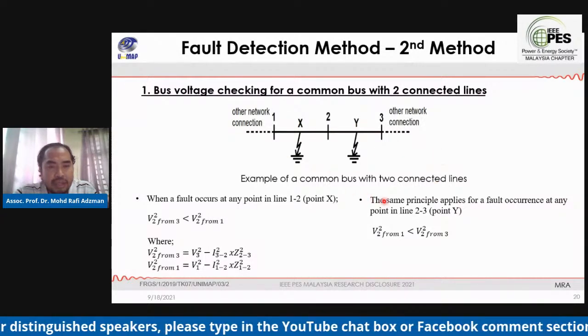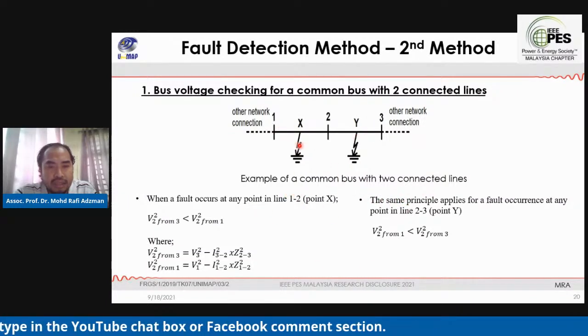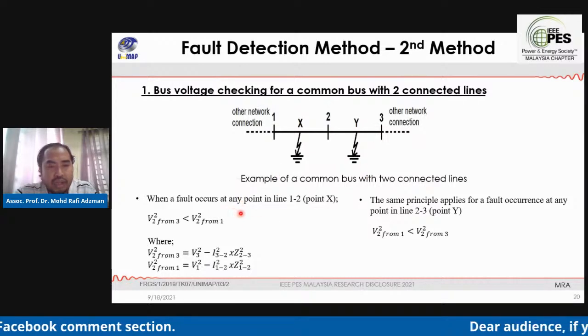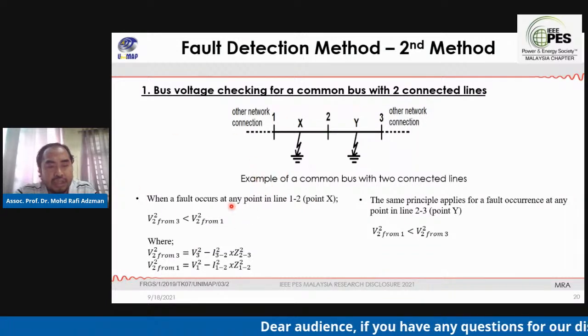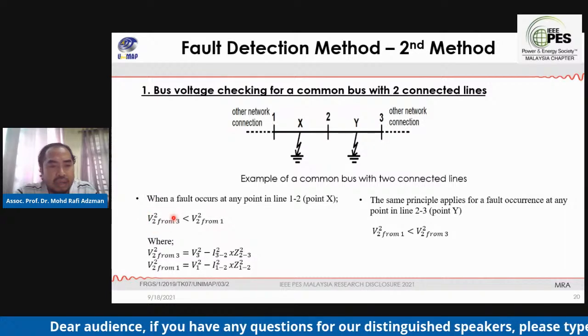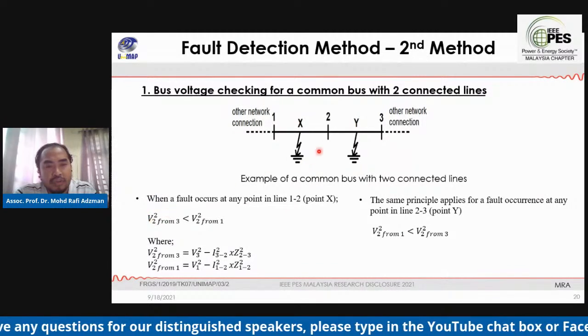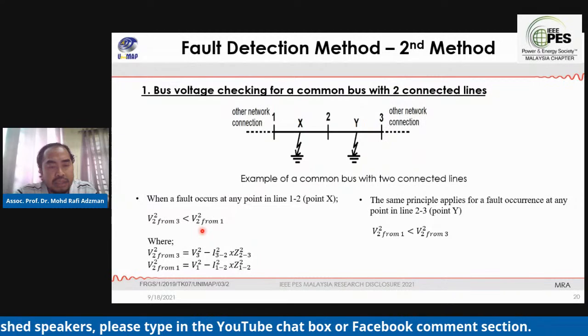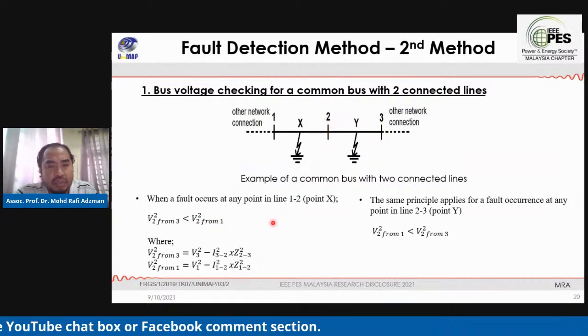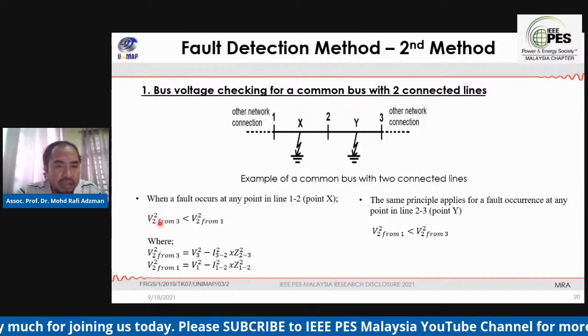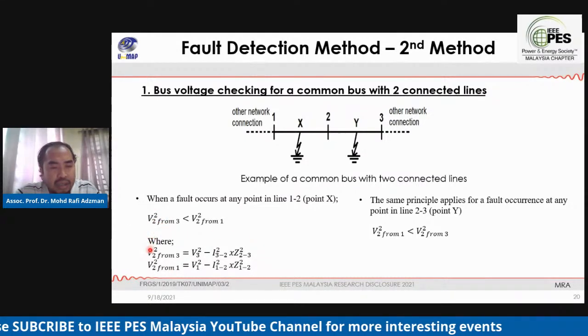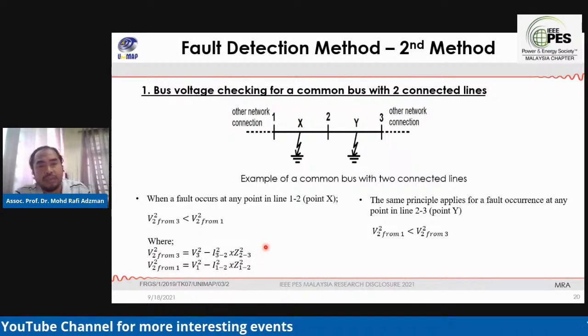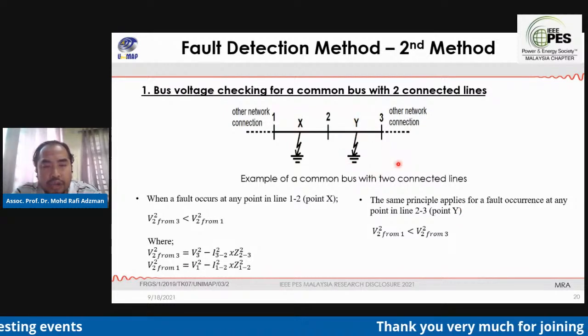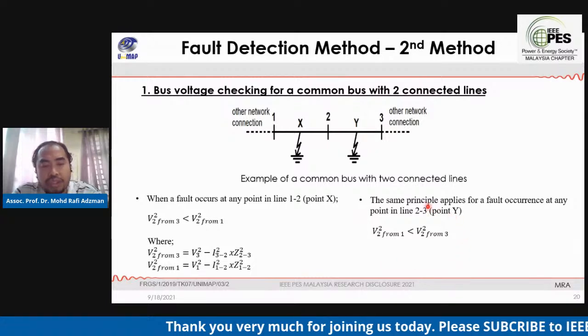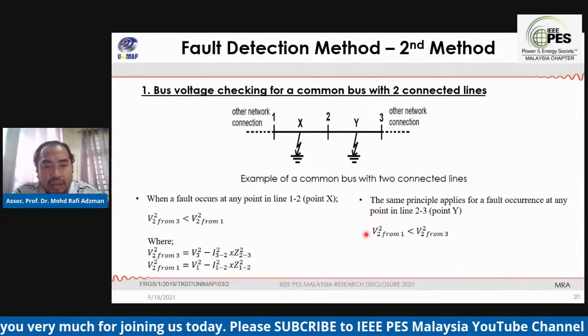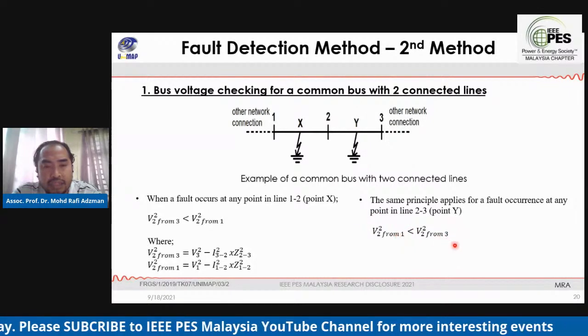For example, here we have three buses: bus 1, 2, and 3. When a fault occurs at any point in line 1-2, point X, we can measure the bus voltage at bus 2 using the negative sequence current measured from bus 3, which is less than the negative sequence bus voltage of bus 2 measured from bus 1. This negative sequence bus voltage can be calculated using this equation. The same principle applies for faults that occur at point Y, so we can use this equation to compare the measurements from bus 1 and bus 3.